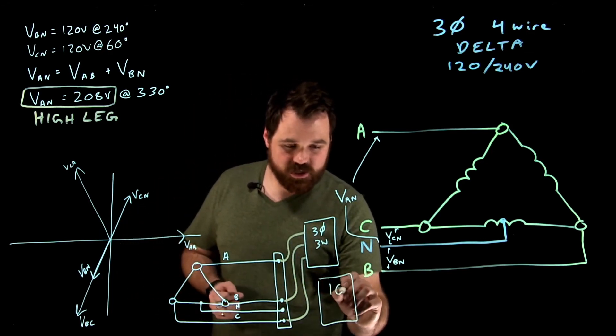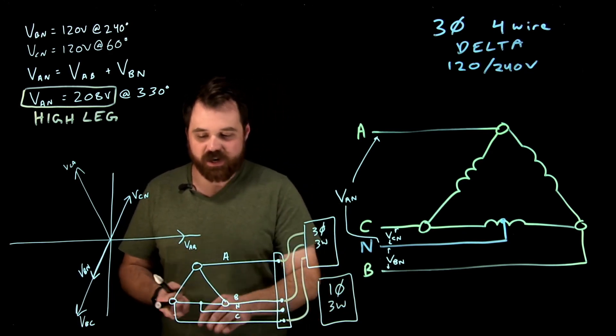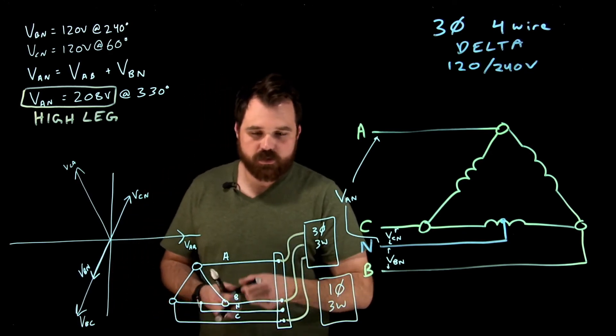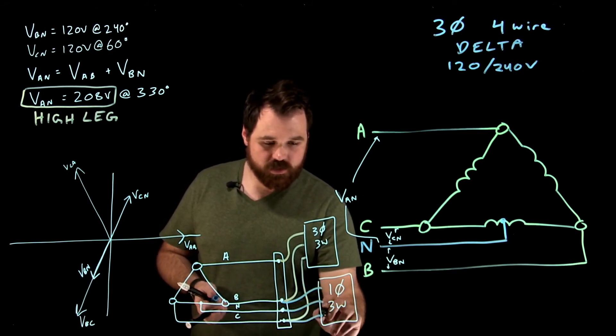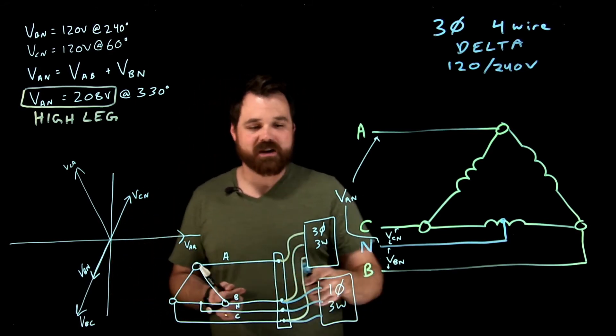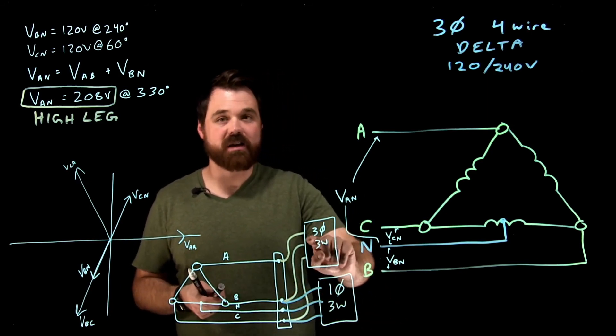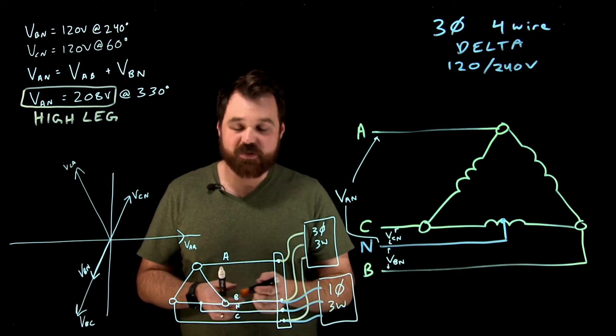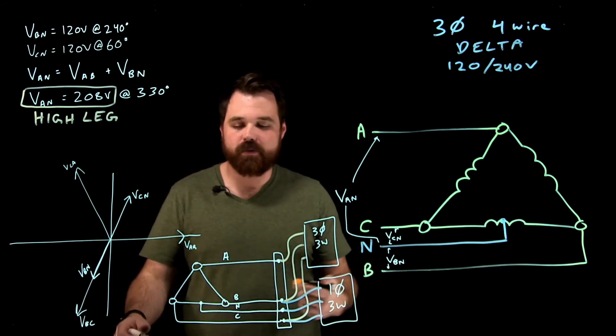It will be a single phase, three wire, 120/240. And it will see B, neutral, and C. It will not have access to A and neutral in the same panel board. So here is A, B, C, and here down here would be B, neutral, and C. So they cannot be in the same equipment.